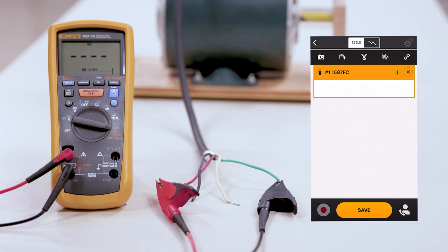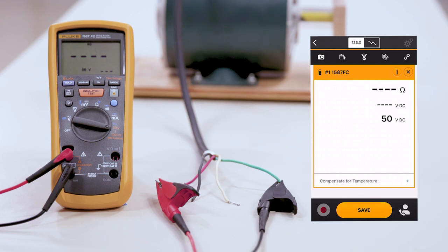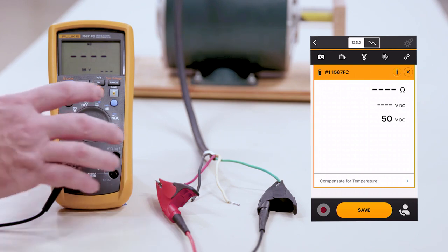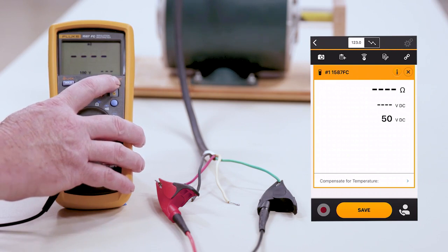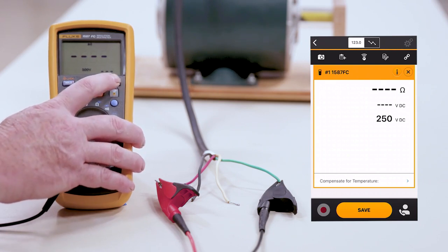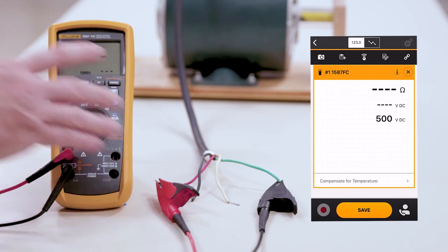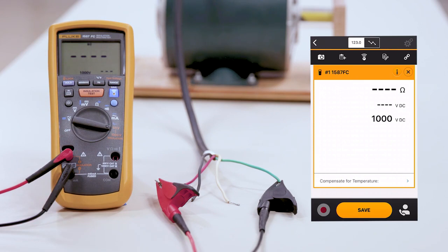Typically in an insulation test, we want to double the value of whatever the rating is for voltage. In this case, this motor is a 480 volt motor. We're going to change the range of our insulation meter to 1000 volts. By doing that, you'll hit the range button.